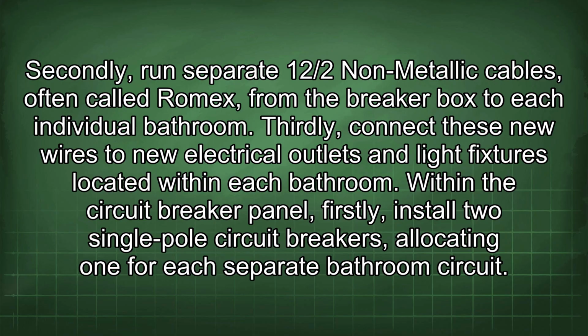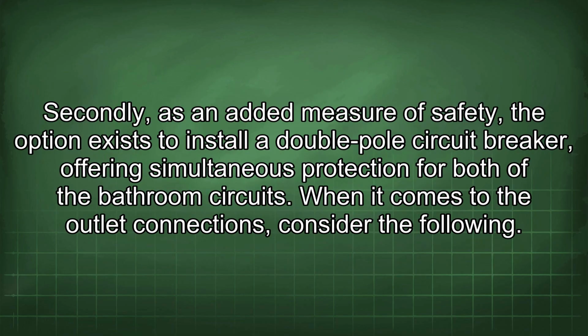Within the circuit breaker panel, firstly, install two single-pole circuit breakers, allocating one for each separate bathroom circuit. Secondly, as an added measure of safety, the option exists to install a double-pole circuit breaker, offering simultaneous protection for both of the bathroom circuits.